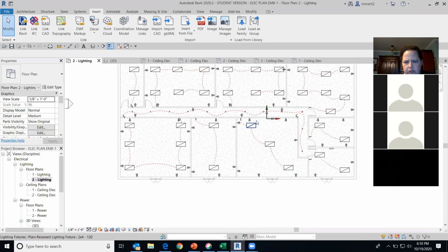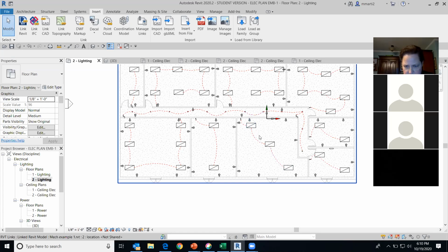On this particular room here, we don't want to do 3 lights. We would want to at least round this up to at least 4. You want to stay away from odd numbered lighting, just because of the uneven distribution of the lights. Say, for instance, in this room, you're going to have a dark area over here, and you'll have a dark area over here.